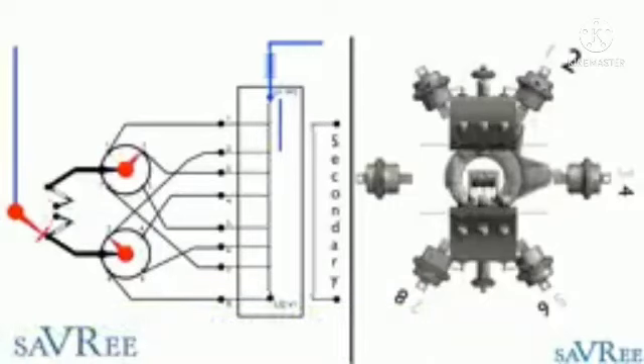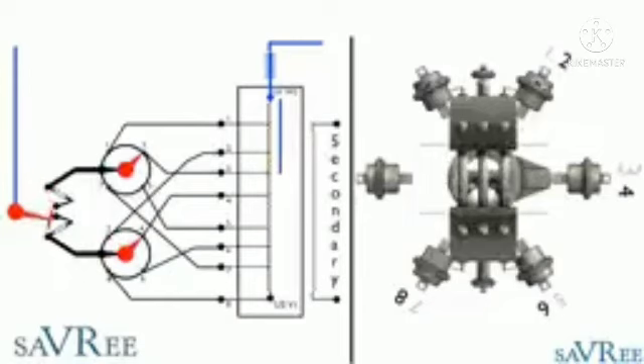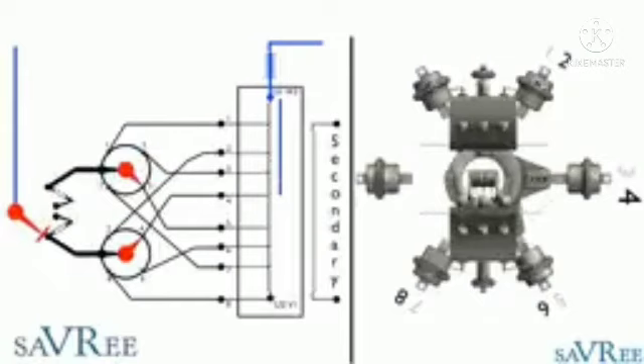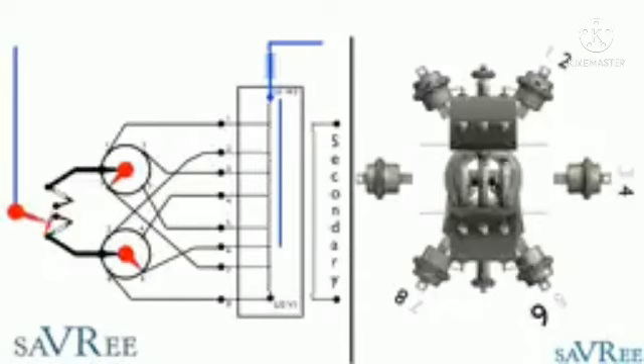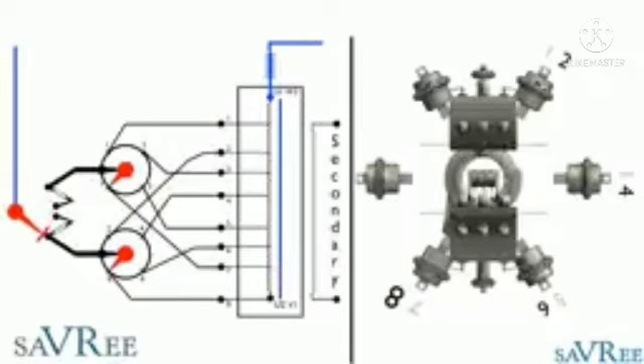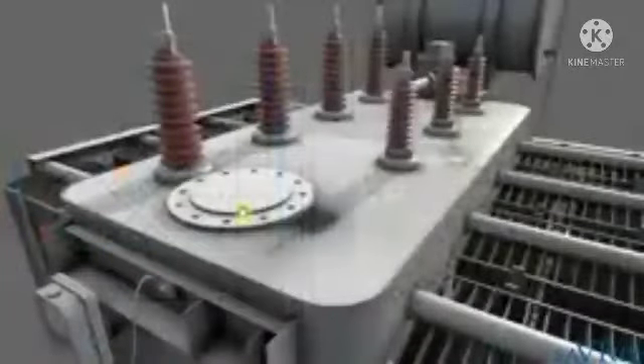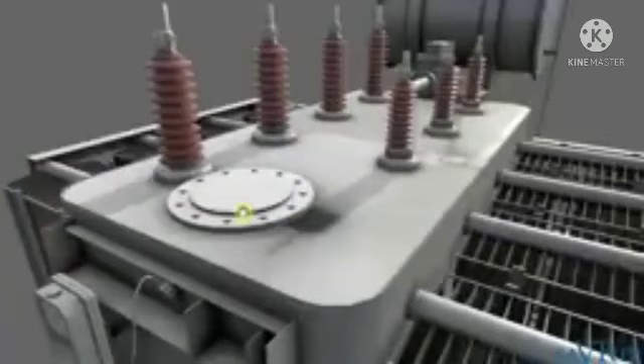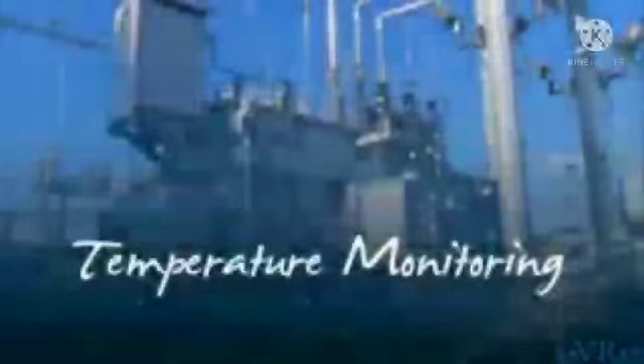The disadvantage to having a tap changer directly within the tank is simply that it shares the same insulating liquid as the transformer. That means that when you sample the insulating liquid and start to look for faults or telltale signs, such as large amounts of acetylene or ethane, you're not going to get much reliable information from your sample. If the tap changer is mounted in a separate compartment or externally to the main tank, then you can sample the main tank. You can then send the sample away for analysis. You can look at the gases that are present within the insulating liquid, and that will give you a good indication as to what faults, if any, are present within the transformer.